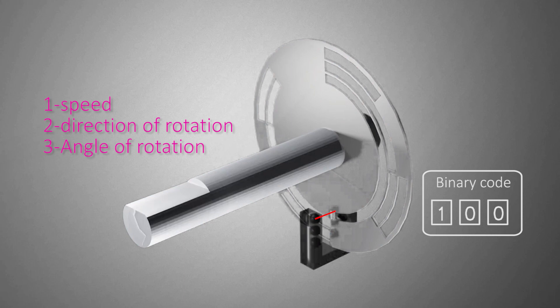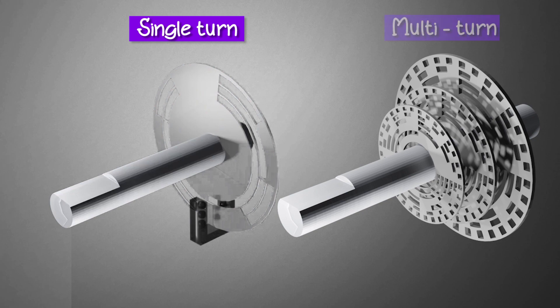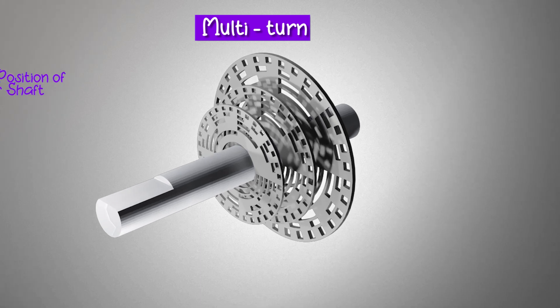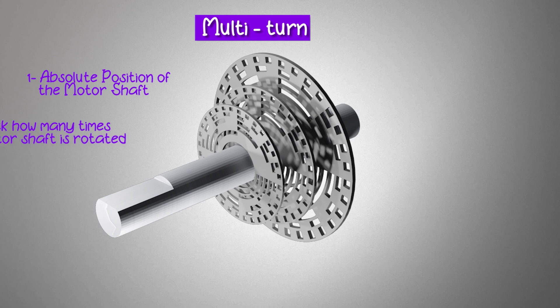From this, speed, rotation, and direction can easily be derived. There are both single and multi-turn absolute encoders available. Multi-turn encoders not only give you the absolute position of the motor shaft but also actively track the number of rotations the motor has made.